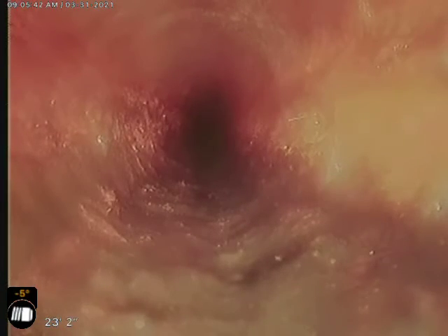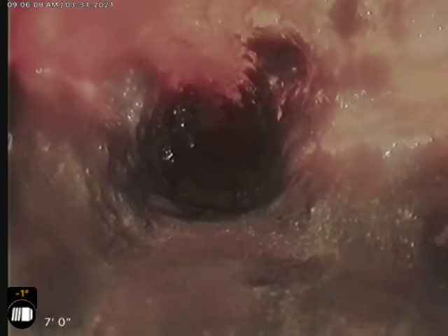I'm going to recommend that we do a descale of the cast iron off of this line because here's that line and it's pretty heavily scaled, and we're getting a lot of nasty sludge out of this. You can see the trough that we've created here, shoving the camera down through this stuff. This is all from the kitchen and the laundry — pretty normal to get this gnarly sludge off of it.